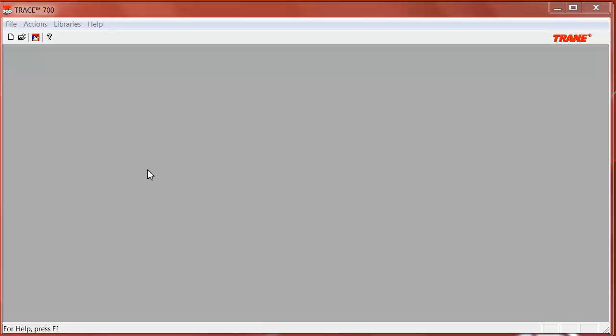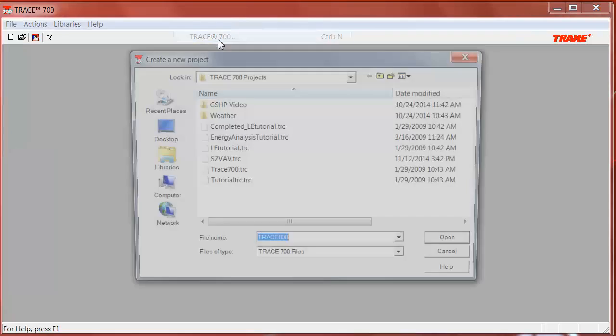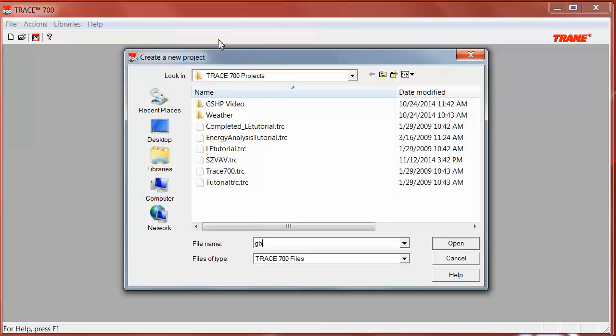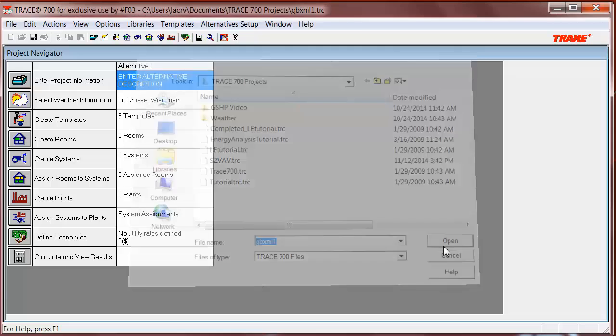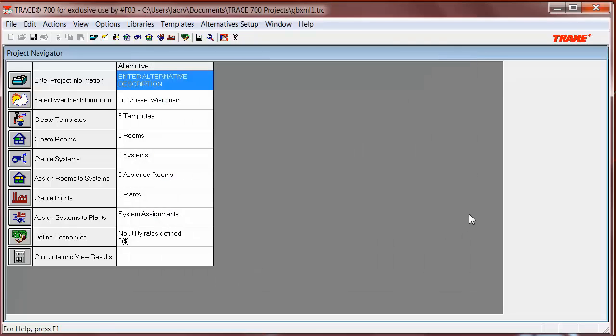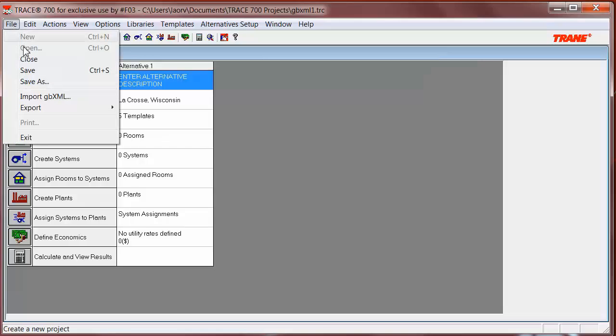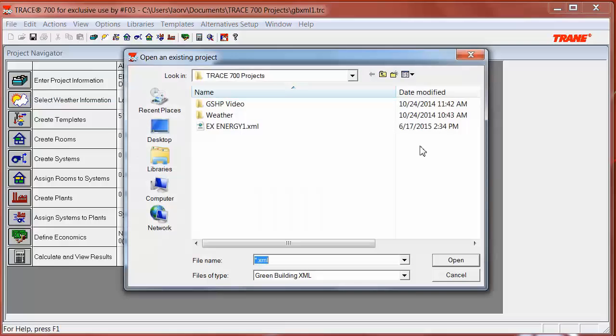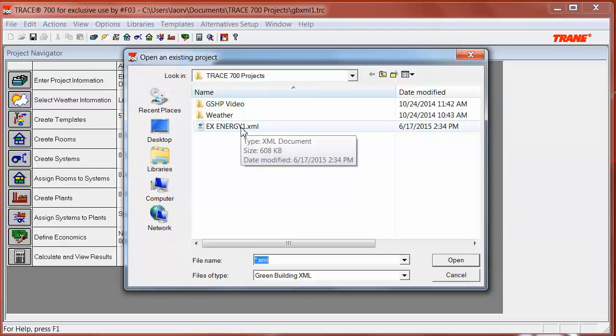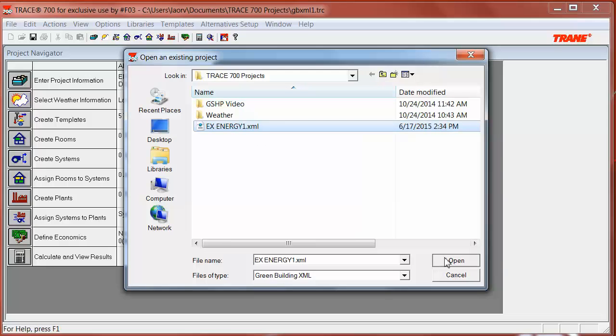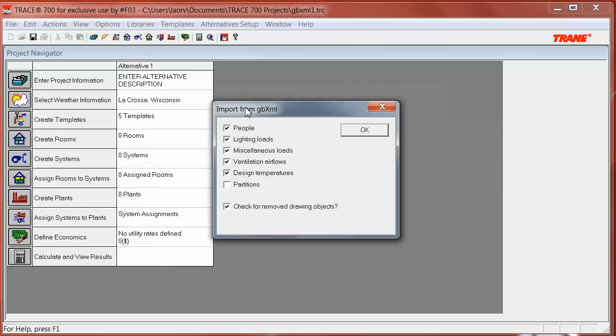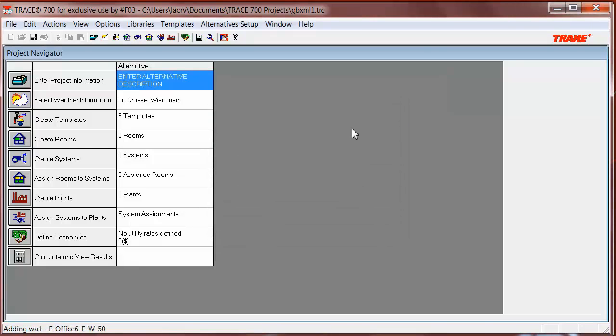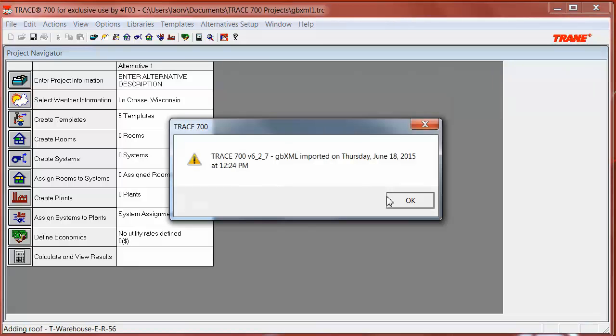Now, let's open Trace and create a new file. You can select templates for the building now or wait to see what is imported from the file. Let's go to File, Import GBXML, and we're going to select the file that was created in Revit. We need to choose what we want to import from the GBXML file. I will select all except partitions. Remember that partitions in Trace are only needed to separate big temperature difference between rooms. Since my rooms all have the same range, I will not select it. And it's done.